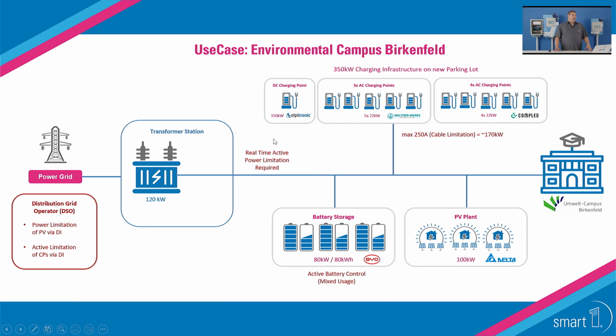So based on the EMS, there were a couple of requirements here. The first one was that we need to have real-time active power limitation for this connection point that goes to the transformer station, because the charging infrastructure is about 350 kilowatts and we only have about 120 kilowatt of available power. In addition, we had a power limitation on this cable of maximum 250 amps, which results in about 170 kilowatts of power available for this connection point. So we needed to make sure that we never draw more than 170 kilowatts over this cable.